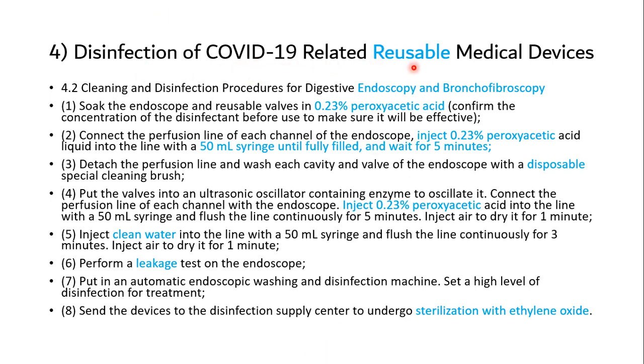Disinfection of COVID-19 related reusable medical devices: cleaning and disinfection procedure for digestive endoscopy and bronchoscopy. Soak the endoscope and reusable valve in 0.23% peroxyacetic acid. Confirm the concentration of disinfectant before use to make sure it will be effective. Connect the perfusion line of each channel of the endoscope. Inject 0.23% peroxyacetic acid liquid into the line with a 50 ml syringe until fully filled and wait for 5 minutes.